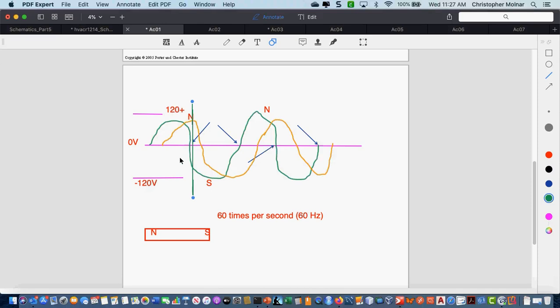So my start winding and my run winding, if I'm using a capacitor, will never be coming through zero at the same time. So if I have 0 volts on the run winding and my magnetic field has collapsed for that split second because it's changing from a north to a south or a south to a north, my start winding still has a magnetic field that is still going to continue moving that motor. It's not as strong of a field because the winding's a little bit different, but it's still going to move that motor. Does anybody have a question on that? That's the whole reason we use capacitors. It provides that extra power, that extra jolt, and that extra energy to make these motors more efficient when they're running. And if it's just a start capacitor, it provides the extra energy that's slightly out of phase to start the motor turning.